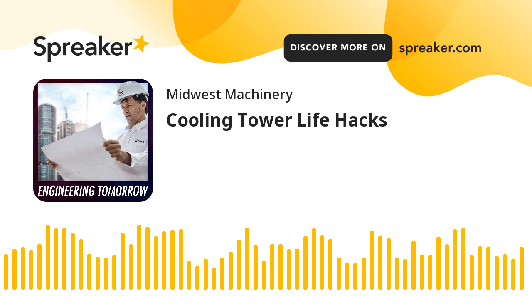All right. So that brings me to our hack number 3, which is, now that we've agreed that we're going to put the gear drive in the cooling tower, for us it's standard. We can provide belt drives, but the gear drive is standard. Where do you put the motor? I'm a huge believer in motors outside the airstream. Because we have a maintenance-free gear reducer, especially when you add the lube lines to it, there's no need to get inside of the cooling tower.